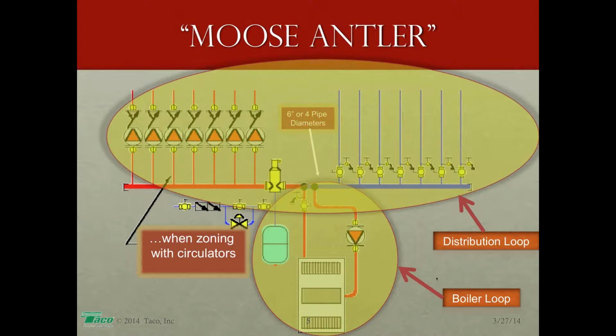You will note if you peer through the yellow, you'll see those two black dots. That's the connection point between the boiler loop and the distribution loop. What makes this quasi-primary secondary is the spacing of those two T's. No more than 6 inches or 4 pipe diameters is optimum. For the same reasons, no more than 6 inches or 4 pipe diameters on a traditional primary-secondary piping arrangement on a cast iron boiler. We want the pressure drop in the common piping, and that's the piping in between those two T's, to be as minimal as possible.